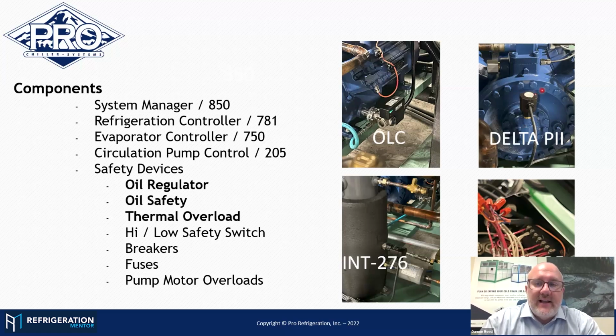This has a little LED on the backside of it that'll light up red. That can be a little misleading, because when the compressor's off and it's not getting a signal, that'll show up as red. It also shows up as solid red when it's in a tripped condition. This white cap that you see here is soft. You don't want to hit it with a screwdriver. It's a little sensitive, but you just push on it with your thumb.